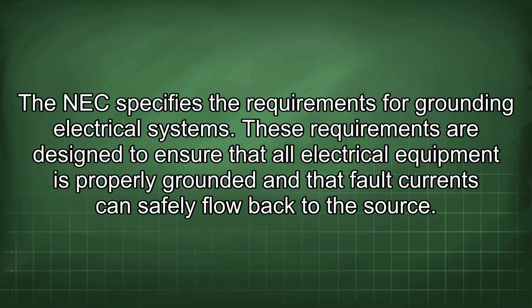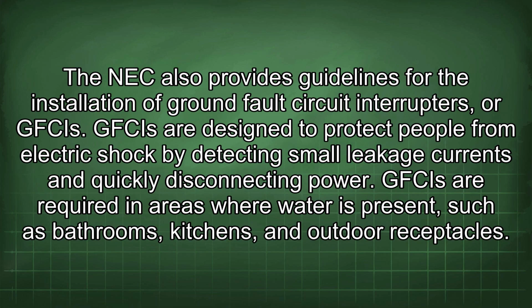The NEC specifies the requirements for grounding electrical systems. These requirements are designed to ensure that all electrical equipment is properly grounded and that fault currents can safely flow back to the source. The NEC also provides guidelines for the installation of ground fault circuit interrupters, or GFCIs. GFCIs are designed to protect people from electric shock by detecting small leakage currents and quickly disconnecting power. GFCIs are required in areas where water is present, such as bathrooms, kitchens, and outdoor receptacles.